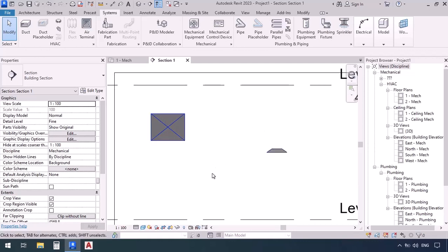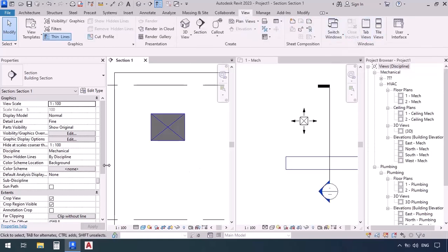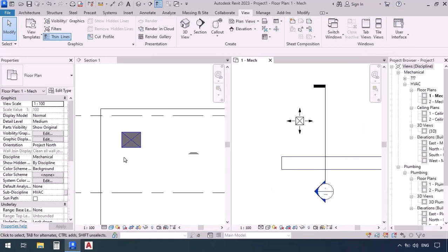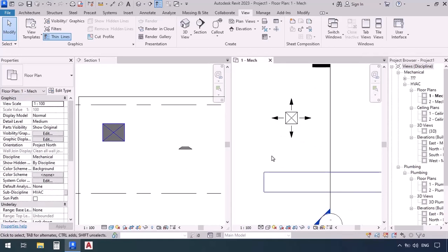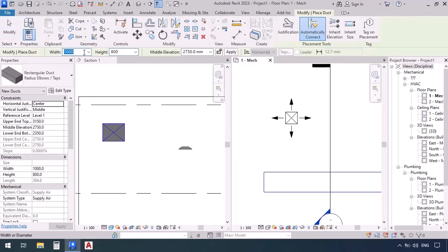Now we want to draw a junction and connect these two — we have multiple ways of doing that. To see the section and the plan at the same time, go to the view tab and click on tile views. Let's minimize the properties window and project browser. On the left we have the section and on the right side we have the plan. While in the plan, go to the systems tab and activate the duct command, entering 300 for width and 300 for height — the connection size of the terminal.